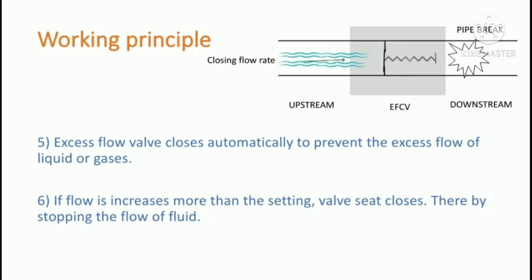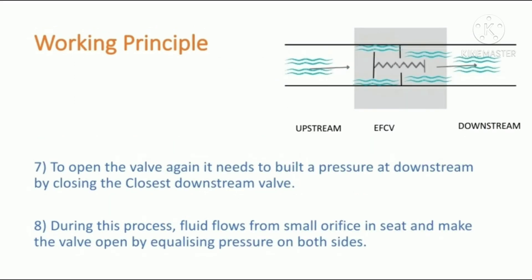The seat closes, thereby stopping the flow of fluid. The excess flow valve is designed for the normal flow rate, peak flow rate, and closing flow rate. The closing flow rate is 20 to 25 percent higher than the peak flow rate. The normal operating flow rate is lower than or equal to the peak flow rate.